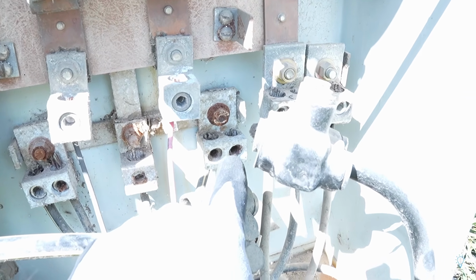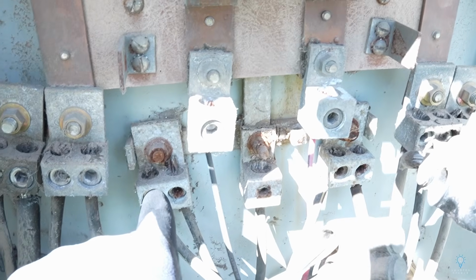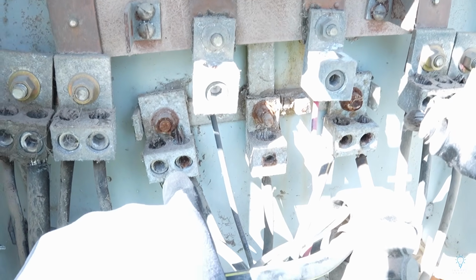So here's my plan. This is the one that for sure needs to be replaced. This is the one that's causing the voltage drop in my house. This one looks pretty bad too, and I did buy a second lug. I mean, that middle one is bad also, but here's the problem. Those bolts that you see right there actually come around to the back side and are right back in here. I'm not even sure if you're gonna be able to see that. I'm having a hard time seeing it myself. But the problem is the pole is there. So I am not going to be able to get to that middle bolt.